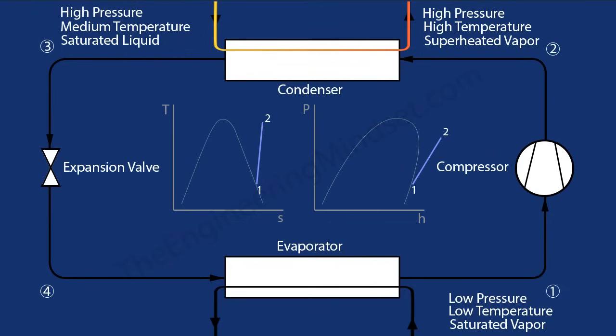Now we can plot Point 3 on the graphs. There has been no change in pressure — the high-pressure side remains constant — but there has been a change in temperature from Point 2 to Point 3. There's also been a change in state: from a superheated vapor (outside the vapor dome) the refrigerant has crossed the saturated vapor line and entered the saturated liquid region.